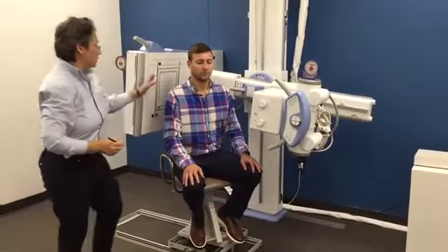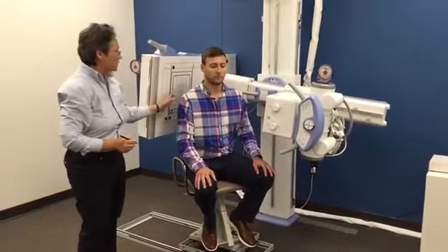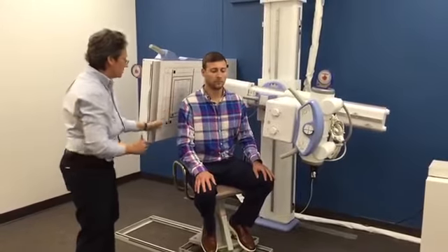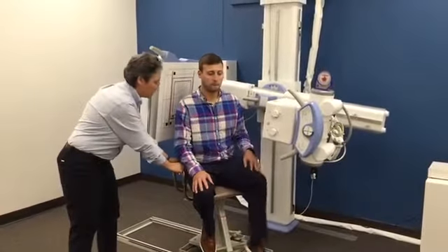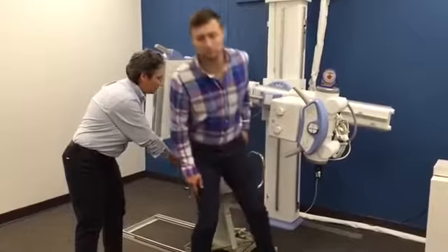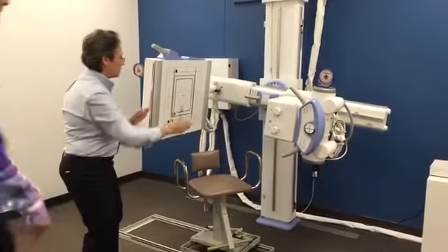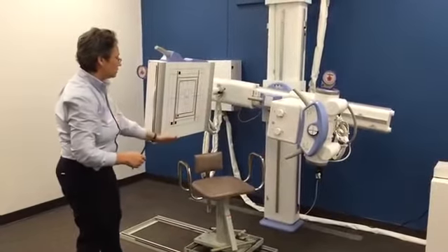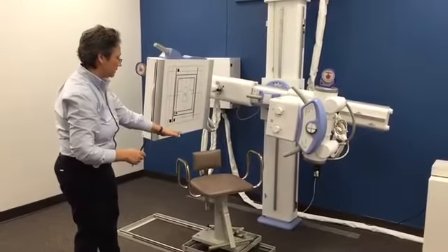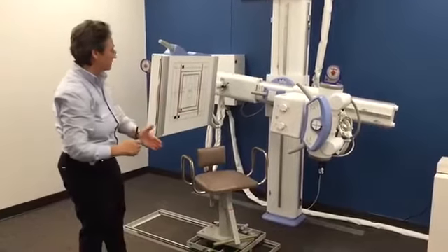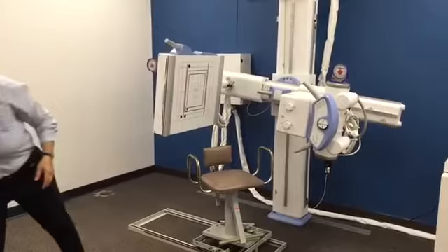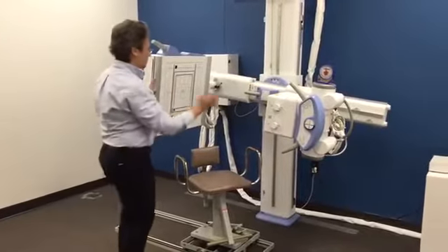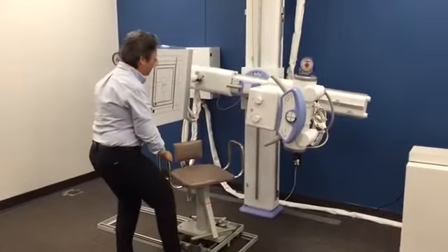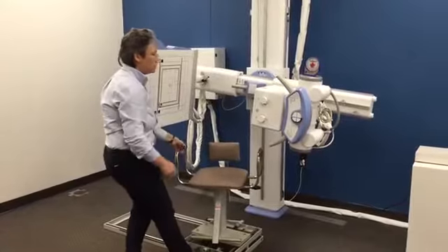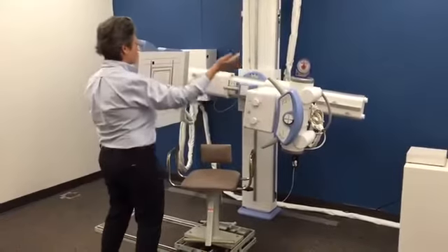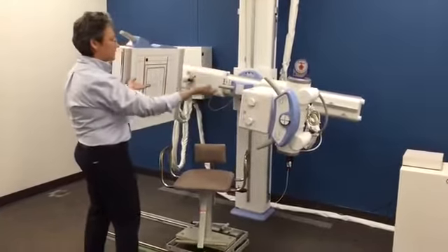Now, with a C-arm unit, once you finish establishing normal head carriage, you want to relax your patient and have him stand up, hold the chair as he stands out. Whenever you move an X-ray unit, that's a C-arm unit, you never want to move it with the patient seated in the chair, because for patient safety, you need to have them stand out. With a C-arm or a straight arm unit, like this is, when you move the tube, the bucky moves. When you move the bucky, the tube moves. It's kind of like a seesaw.